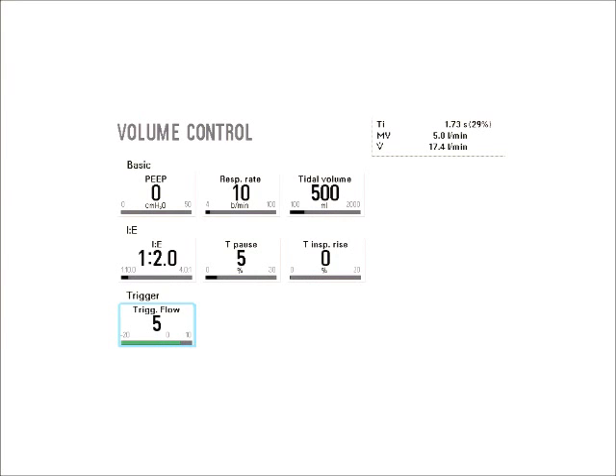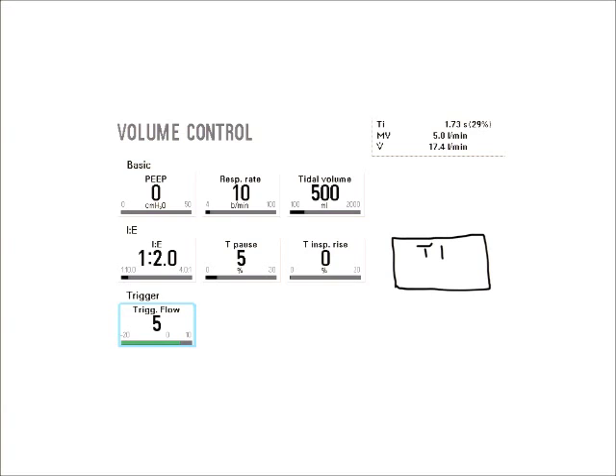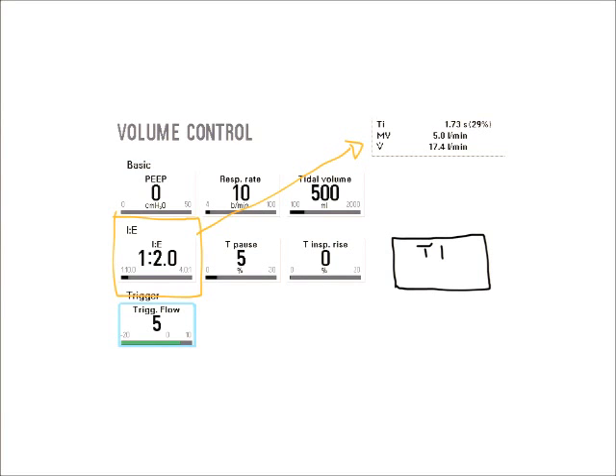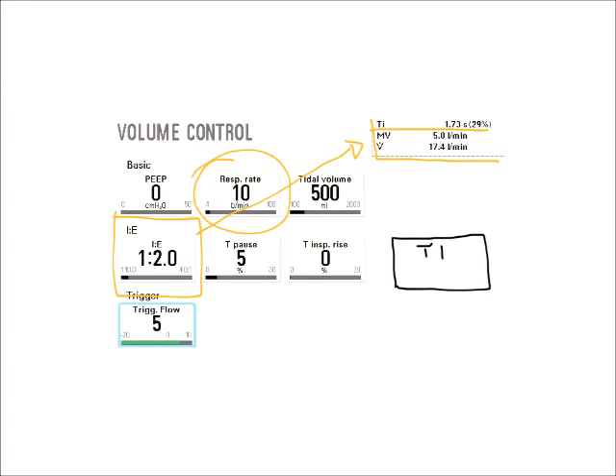Now here's a screenshot of volume control ventilation. And we do not actually see a setting that the operator set. So there isn't a box over here that says TI. However, for TI here, instead of that, the operator actually will set the I:E ratio, which in turn calculates an inspiratory time for me based also on my respiratory rate. So this is just a little smart window. It shows measured values calculated from what set points the operator puts in.